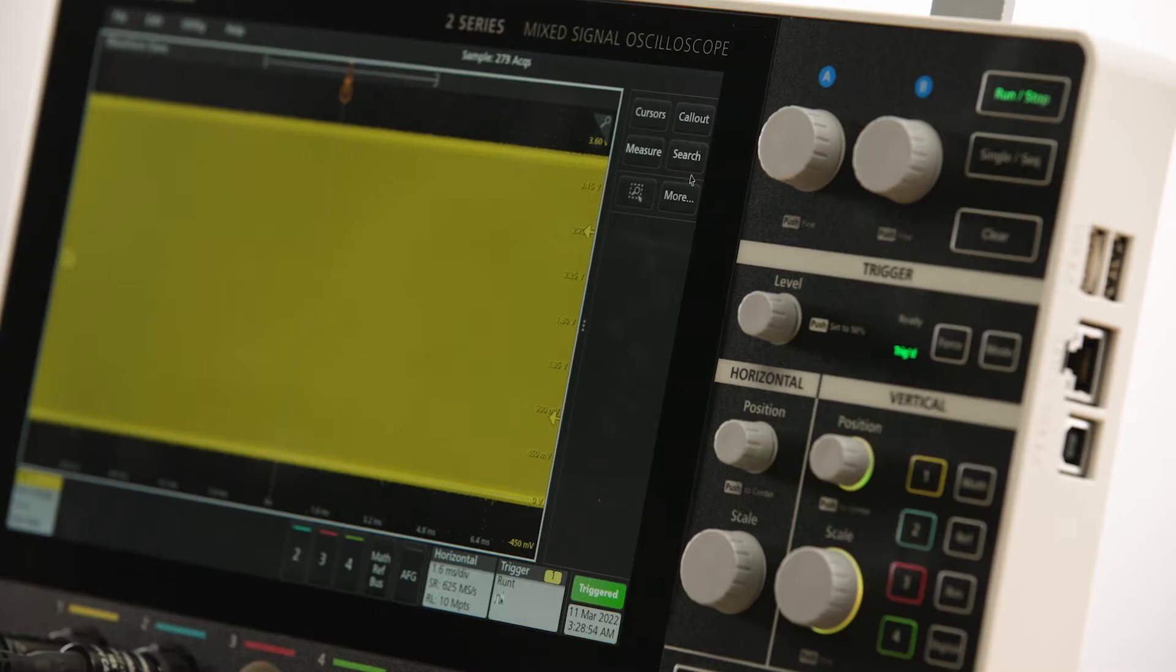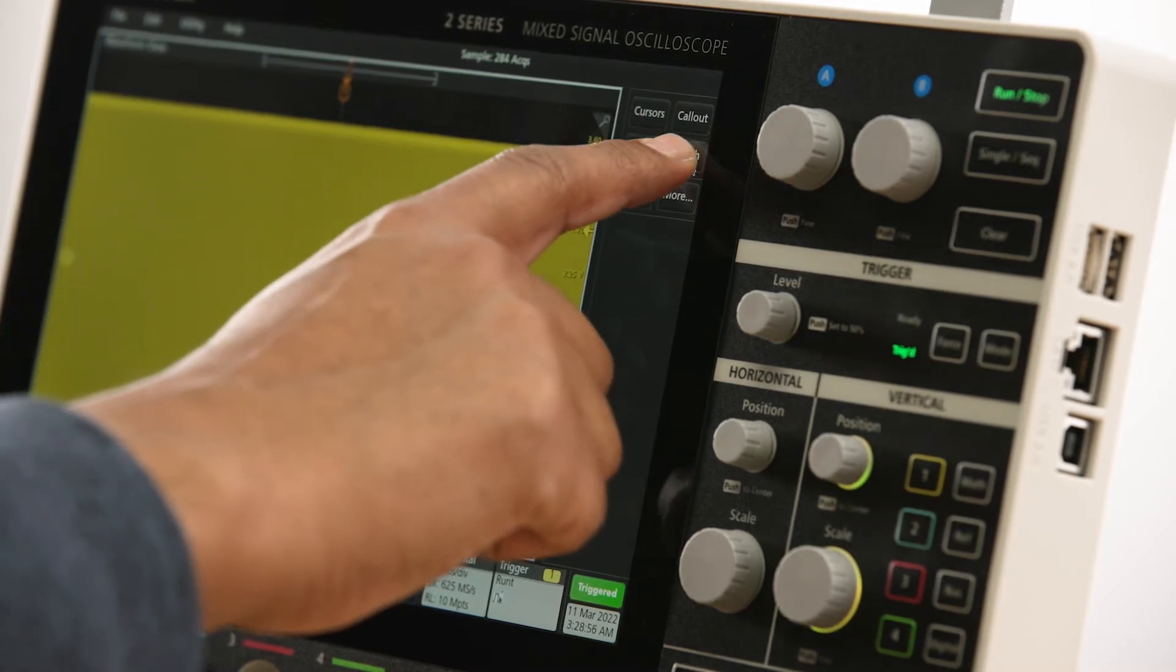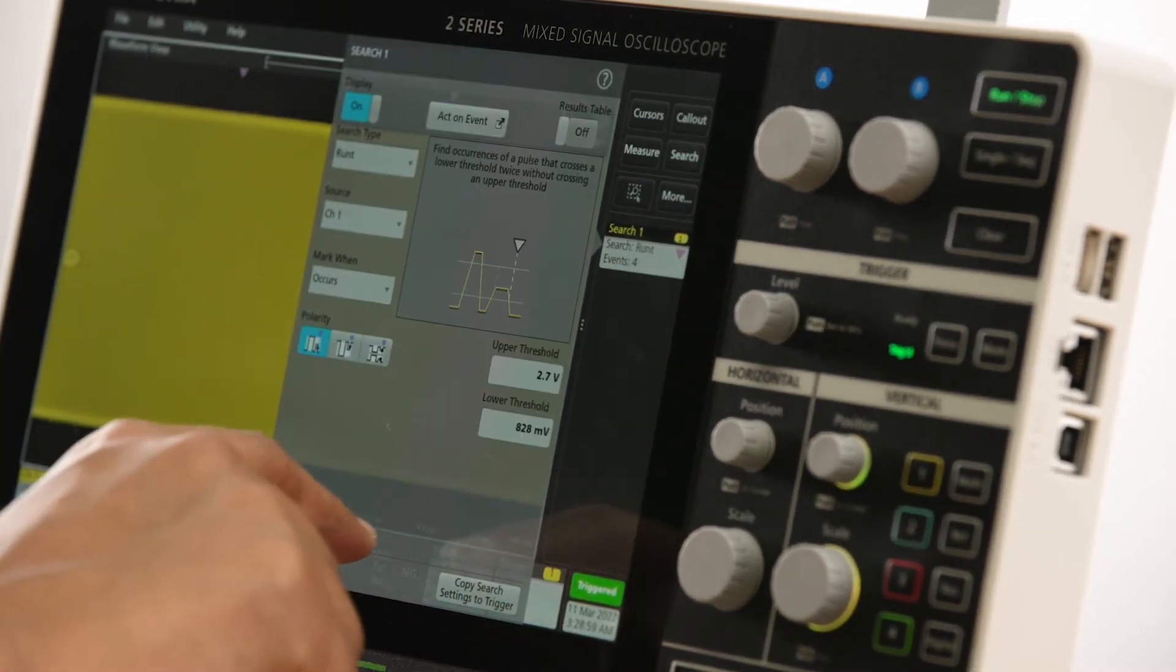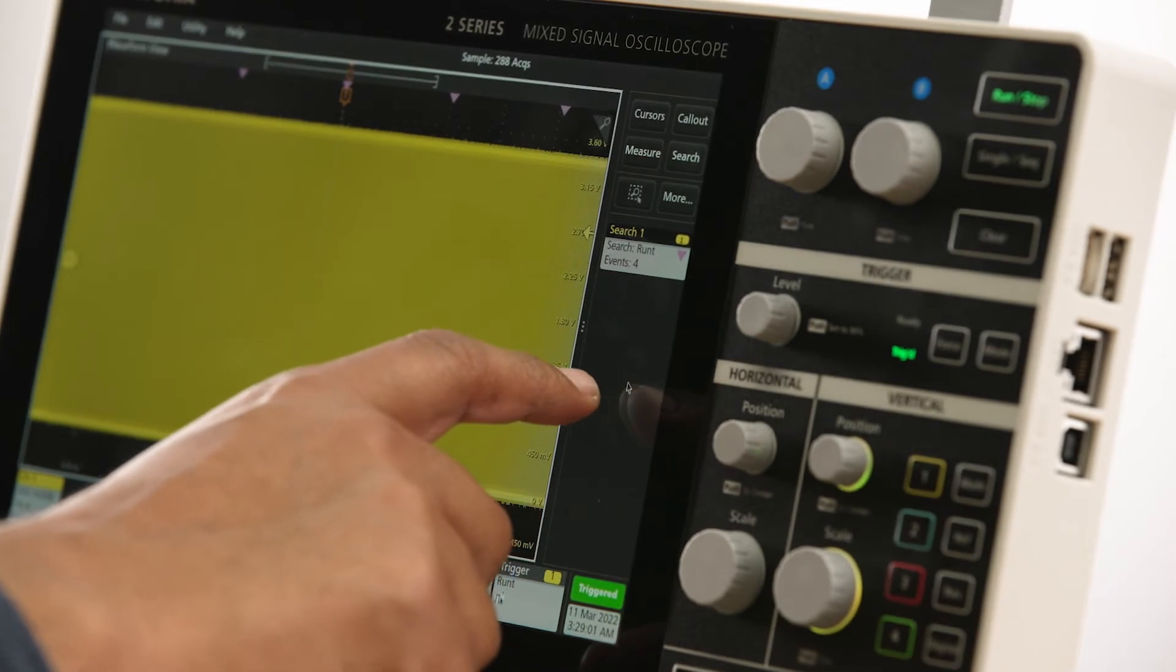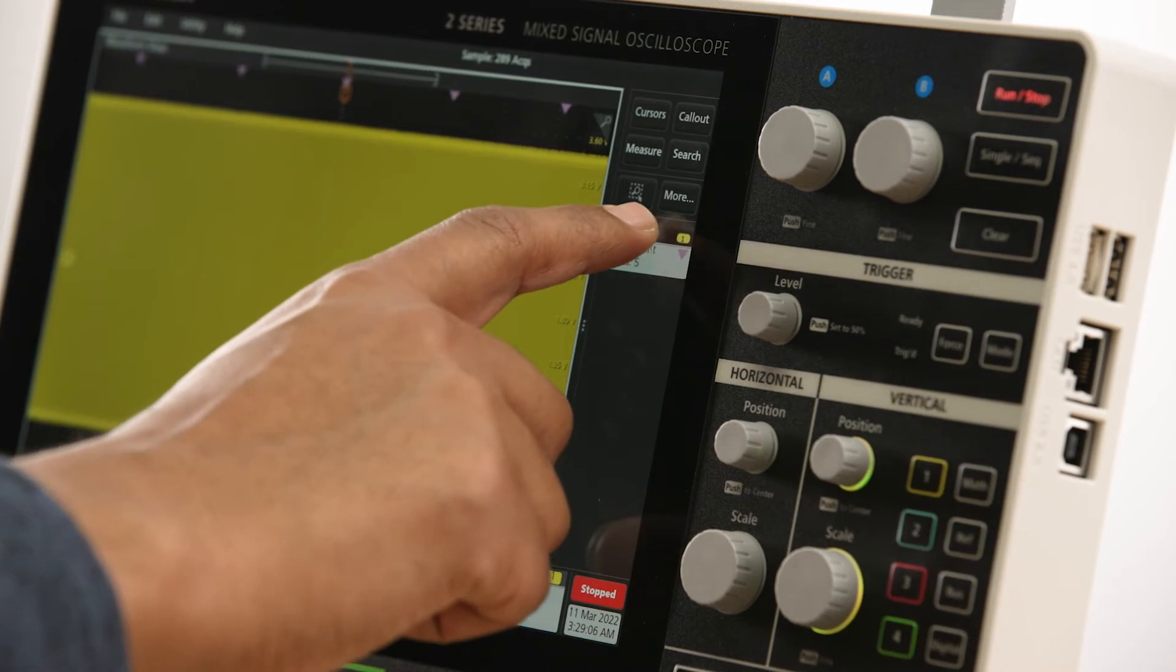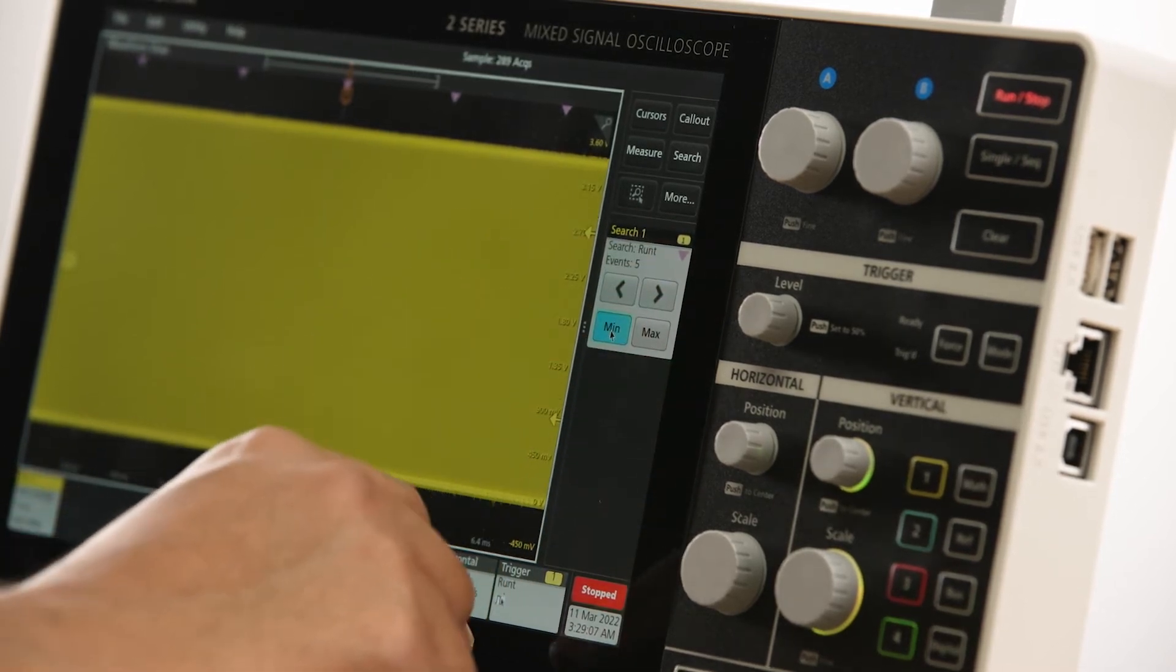We can quickly set up a search definition to see if there are other runts like the one we triggered on within the acquired waveform. The results of the search are shown on the search badge and we can see that there are several runts in the acquisition.